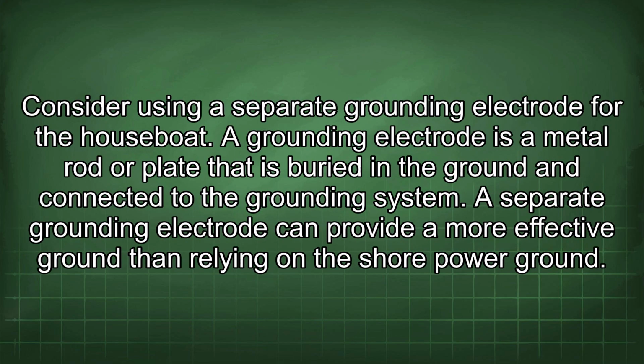Consider using a separate grounding electrode for the houseboat. A grounding electrode is a metal rod or plate that is buried in the ground and connected to the grounding system. A separate grounding electrode can provide a more effective ground than relying on the shore power ground.